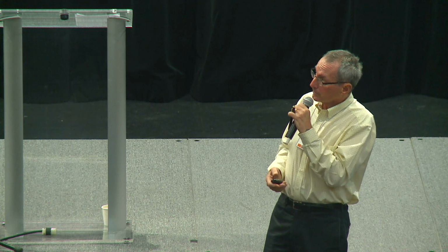So you might say, well, it's an oversized heat pump. The sizing of a heat pump isn't quite the same as sizing a boiler. You can put a 4-ton heat pump in a 3-ton house, especially now with inverter compressors. The compressor can adjust for the load. But the takeaway, 2 takeaways, you're going to do better at low water temperatures, and it's not a throwaway to say, here's a baseboard system, I can't put an air-to-water heat pump in there. You can. Your performance is going to be lower.